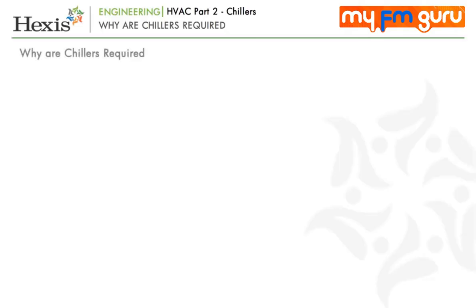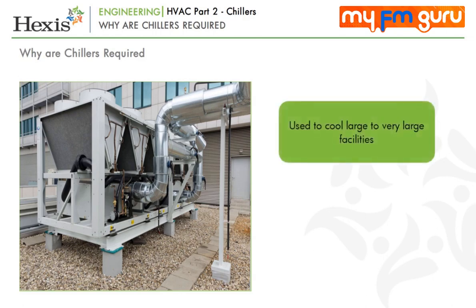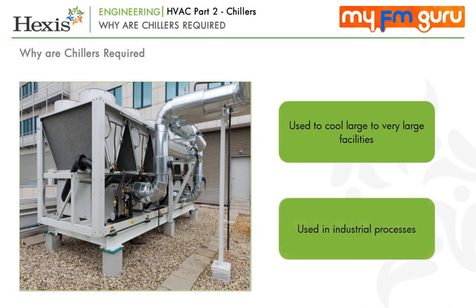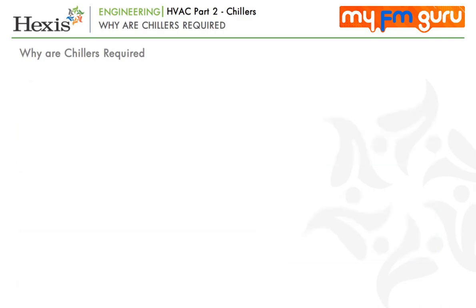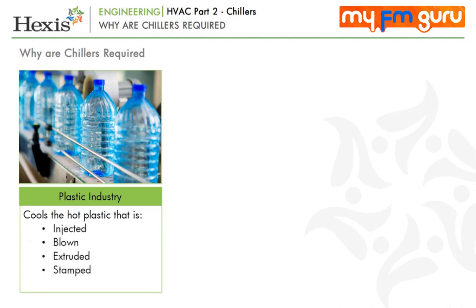Now let us understand in detail why we need chillers. As we have learned in Part 1 of this HVAC module, chillers are used to cool large to very large facilities. It is much easier and cheaper to use water than running refrigerant piping all over the building. Chillers are also used in industrial processes — either to provide cooling to equipment that generates a lot of heat but needs cool environments for operation, or to provide specific temperatures with high precision for certain processes. For example, in the plastic industry, a chilling system cools the hot plastic that is injected, blown, extruded or stamped.